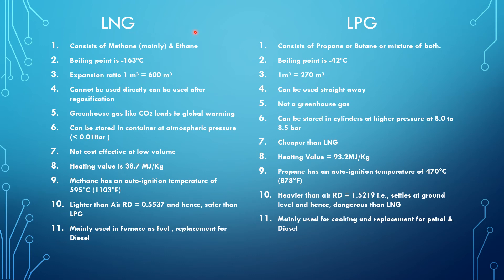Now we can see the main differences — advantages and disadvantages — between LNG (liquefied natural gas) and LPG (liquefied petroleum gas). LNG mainly consists of methane and a little ethane, whereas LPG is propane-based or butane-based, or a mixture of both. The boiling point of LNG is minus 160 degrees centigrade, while the boiling point of LPG is minus 42 degrees centigrade. The expansion ratio of LNG is 1 meter cube giving 600 meter cube of natural gas.